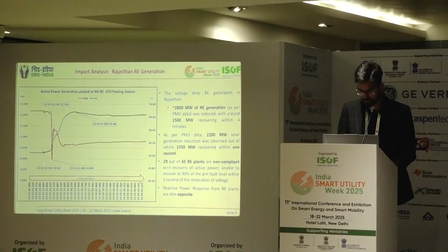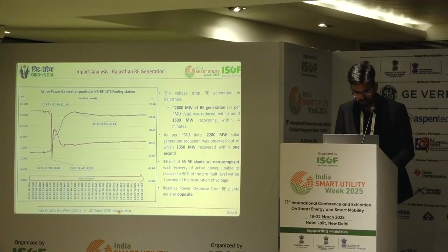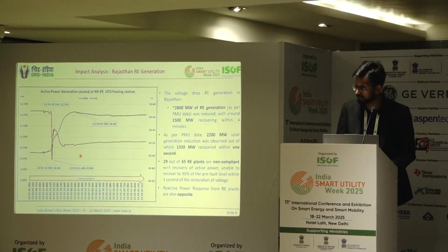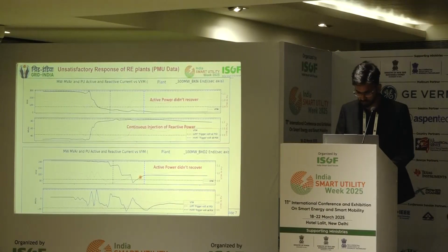During this event we observed the behavior of the RE already connected in the system. As you can see, this is the total RE generation pool in our RE complex in Rajasthan, mainly 5, and now we have 7 pooling stations. We observed that due to the decline in voltage, there was a reduction in active power. But as per the CEA connectivity standard, it should have recovered 90% of its generation within 1 second. But that was absent from the data of these plants. So we dived a little bit more into plant-wise analysis of the system.